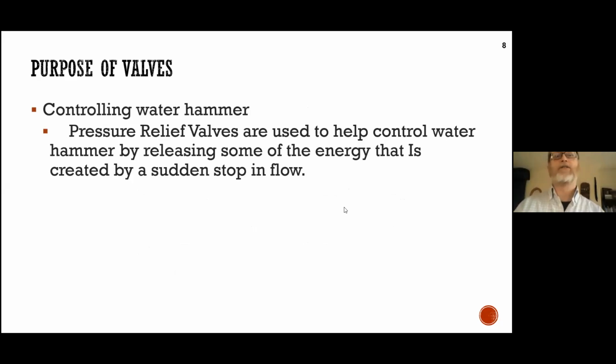Styles of pressure relief valves. Pressure relief valves, altitude control valves, or pressure regulating valves can all be, and typically are, control valve style, some butterfly, but we can plumb those valves in such a way that we can actually use their style of construction to do remote work for us, whether it's preventing a surge wave of pressure coming back against a pump and discharging it, whether it's opening to allow a reservoir to fill, closing when it's full, or allowing pressure to be regulated through a change in elevation.